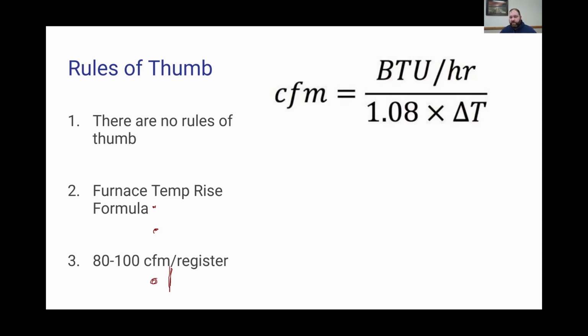So his solution was to either put a booster fan in that 8-inch duct so that it can move closer to 500 CFM, or replace the 8-inch duct with a 12-inch duct, which would also allow it to move that. So duct design, when you're talking about SEER ratings and equipment performance, is key.